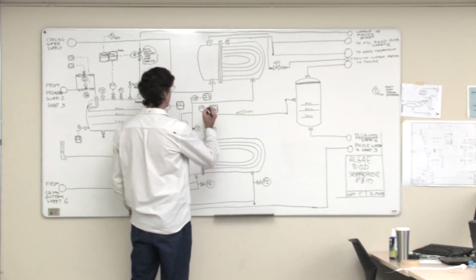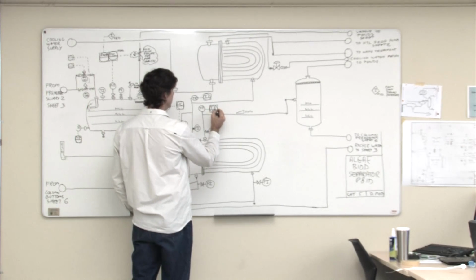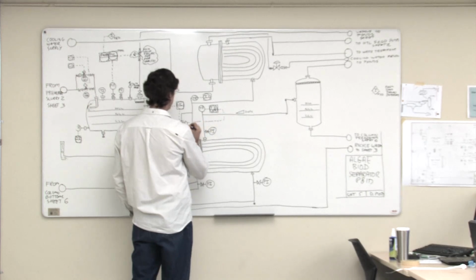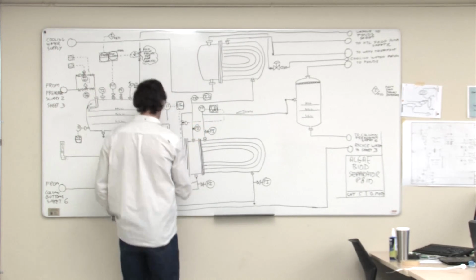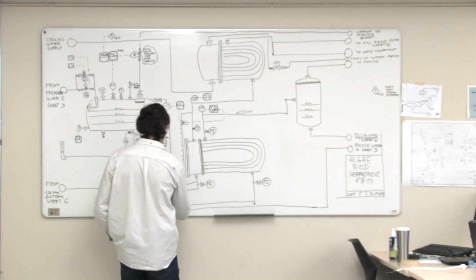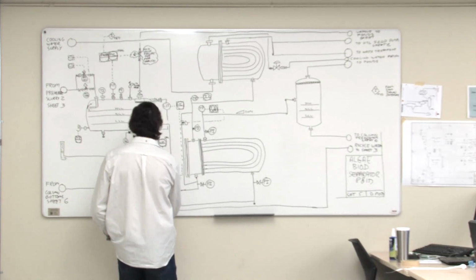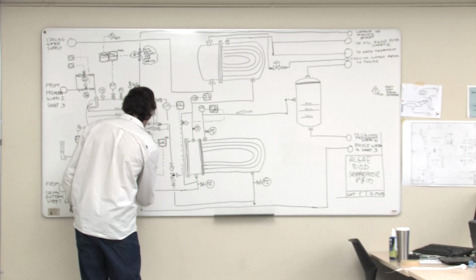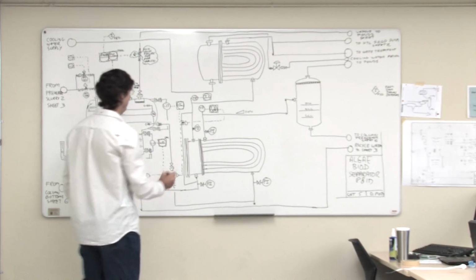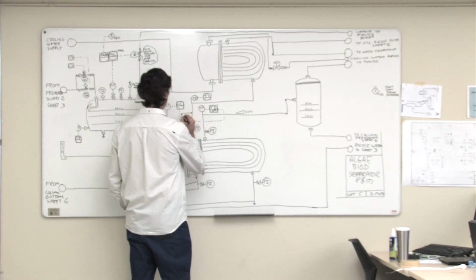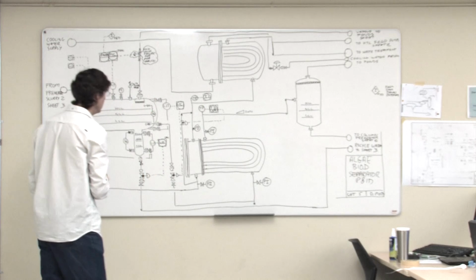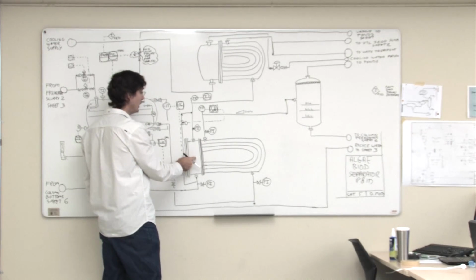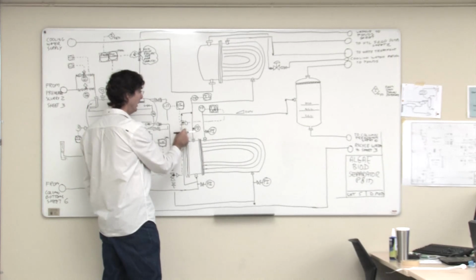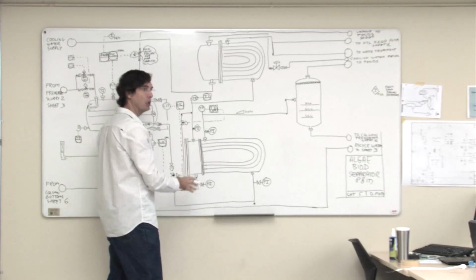So now what we can do is, depending on which one we think is more important, maybe this one. Make that a fail-closed valve. I forgot my failure positions on these valves too. Okay. So yeah, a bypass. That one is a little bit of lateral thinking. The problem with that is if you have a really low pressure drop through this heat exchanger, then it's quite hard to actually get the fluid to bypass the heat exchanger. This heat exchanger has to have a fair bit of pressure drop for that game to work.